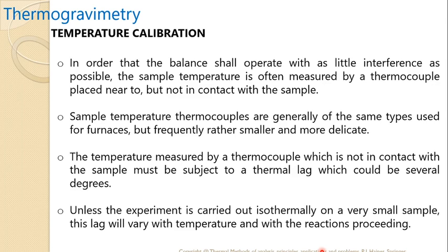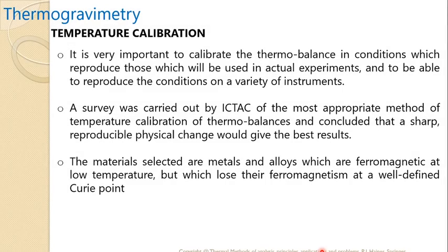Unless the experiment is carried out isothermally on a very small sample, this lag will vary with temperature and with the reactions proceeding. It is very important to calibrate the thermobalance in conditions which reproduce those which will be used in the actual experiment, and to be able to reproduce conditions on a variety of instruments. A survey carried out by ICTAC of the most appropriate method of temperature calibration of thermobalances concluded that a sharp, reproducible physical change would give the best result.